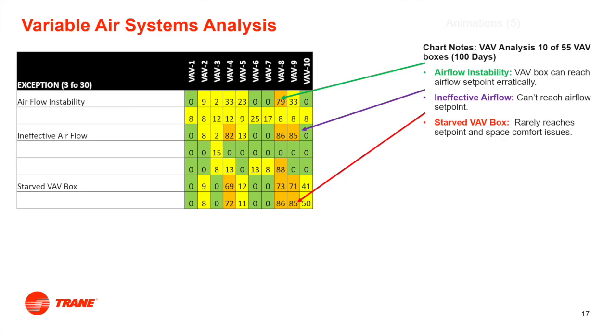So you're starting to see a trend where, out of 55 VAV boxes, these are the ones that are a problem. It used to be if I had an air handler VAV system with issues, I'd need to hire a controls guy, a test and balance person, and go through and recommission the entire thing—tens of thousands of dollars to do that. In this case, I can simply say here's what we need to do: service these outlier boxes and everything should come back into line. I'm going to show you some more data that supports that.